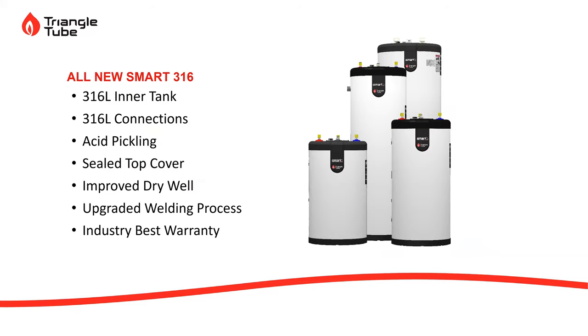Indirects, smart tanks, 316 stainless steel. So this is a tank within a tank, so it's a little bit different with the coil. We get a little bit better output with it. Comes with an aquastat built into it. Our boilers all come with 12K sensors. All of our sensors on our boilers that we'll go through are all 12K. But our boilers do come with a 12K sensor, so you could remove this aquastat and dump in our sensor if we want to utilize some of the post-purge functions as well, too.